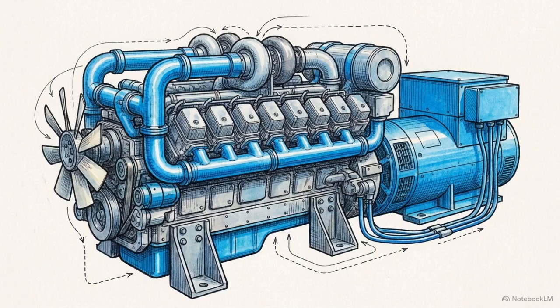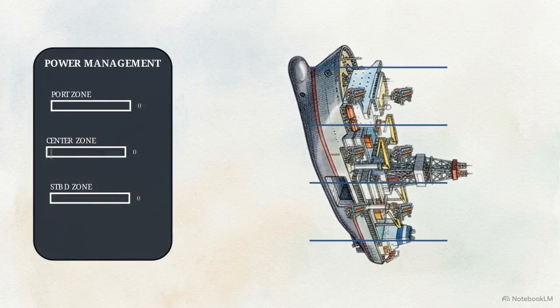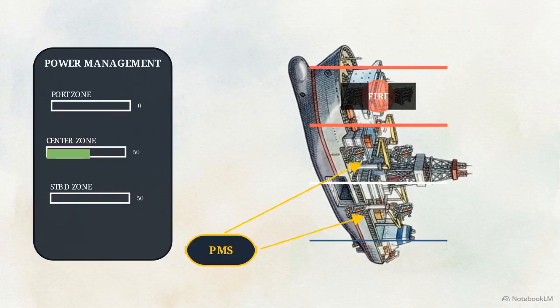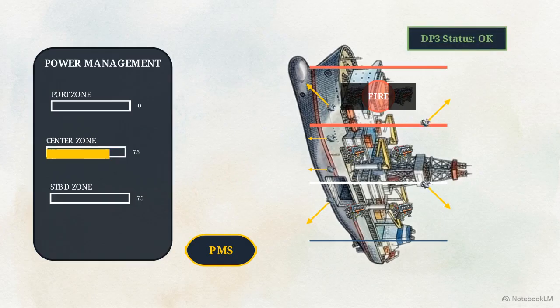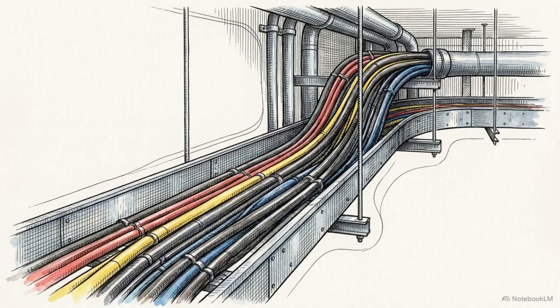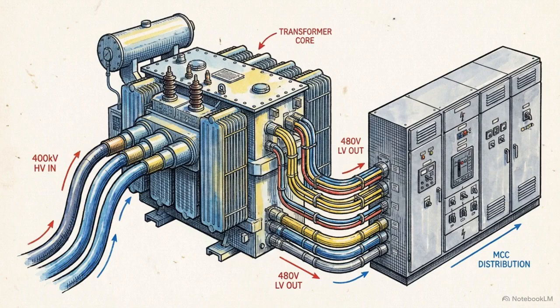The vessel generates 42 megawatts of power using 6 Wärtsilä engines. To meet DP3 requirements, these 6 engines are split between 3 separate rooms. A60 fire-rated bulkheads ensure a catastrophic event in one zone cannot spread. If one room is lost, the power management system commands the remaining engines to increase output, preserving thrust. The power is distributed at 11 kilovolts. Generating at high voltage allows the ship to move massive loads while keeping physical cable sizes and electrical current manageable.